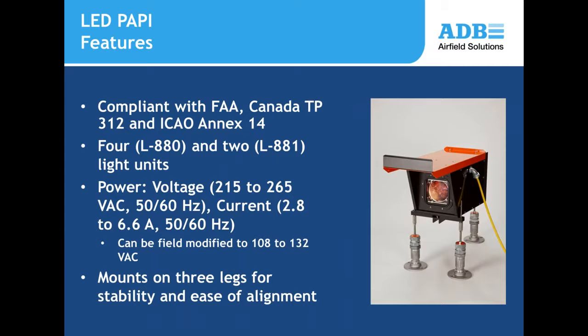The LED PAPI is compliant with FAA, Transport Canada, and ICAO specifications. This covers a four-box PAPI system (L-880 in the FAA market) or an abbreviated two-box system (L-881). For voltage-driven PAPIs, mostly used in the US market, input voltage is 215 to 265 volts at 50 or 60 Hz, modifiable in the field to 108–132 volts AC, or current-driven from a series circuit operating between 2.8 and 6.6 amps.